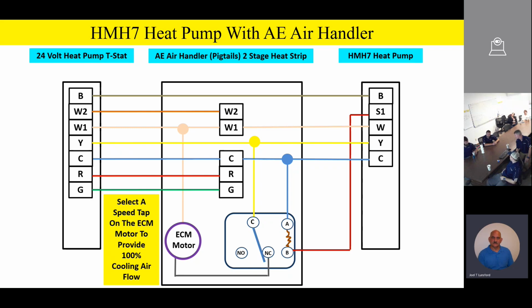The normally open contact on the relay is going to go over, and on the ECM motor, we're going to select a speed tap to give us about 60 to 65% airflow. Now remember, team, on the product, this might be medium high, it might be medium speed tap, it might be medium low. So you're going to have to measure your airflow and determine how much airflow you've got on your different speed taps. And you'll need to select the speed tap on the ECM motor that's going to give you about 60% airflow. And we're going to see here in a minute or two, when we energize that relay and we switch the relay, we're actually going to be going to a lower speed command, or more specifically, a lower airflow command.